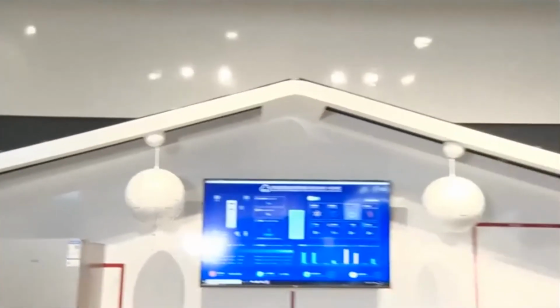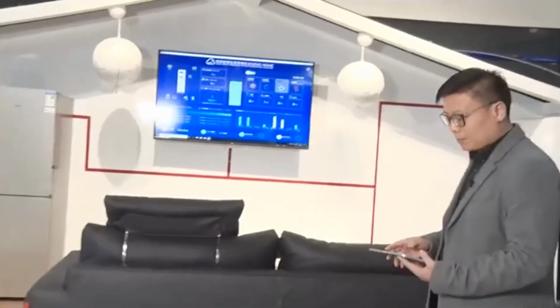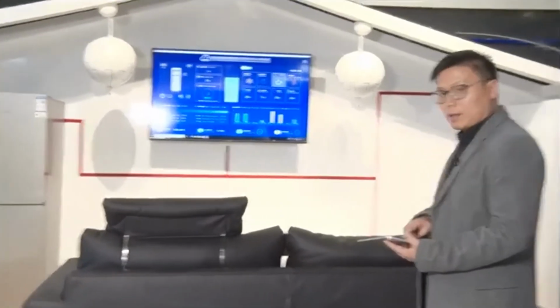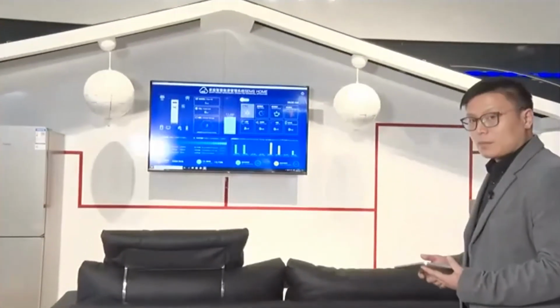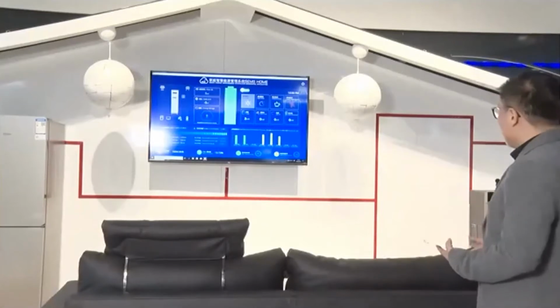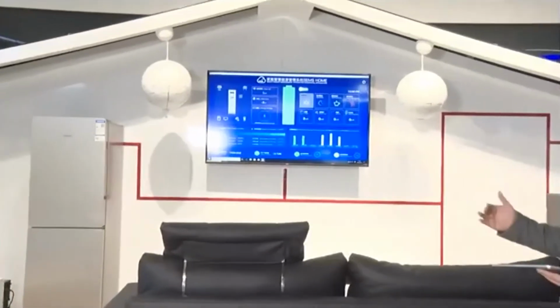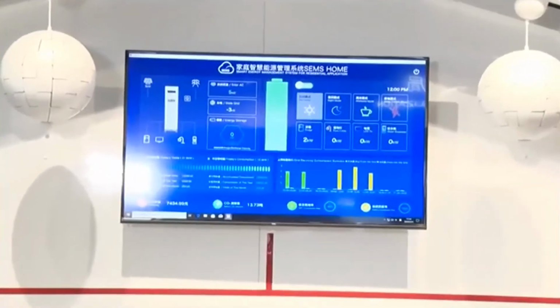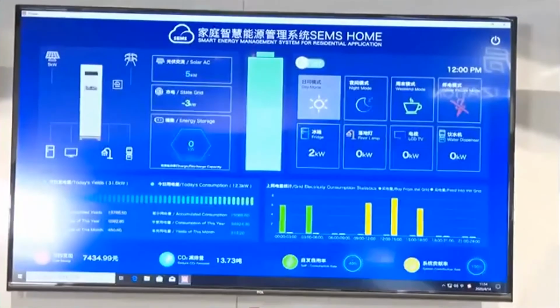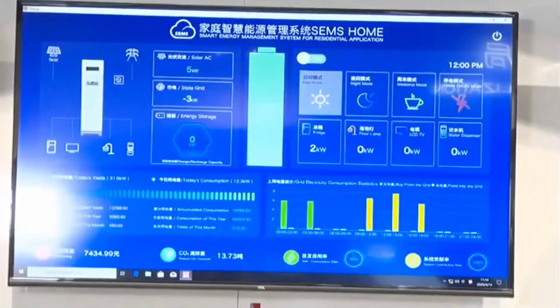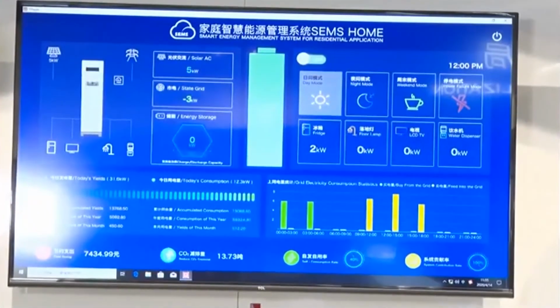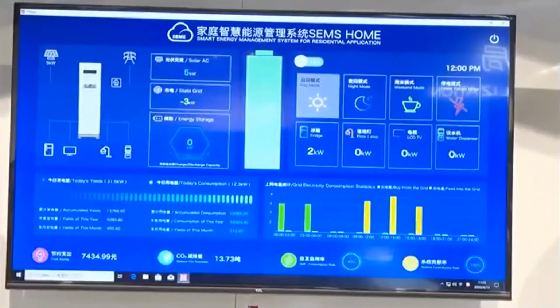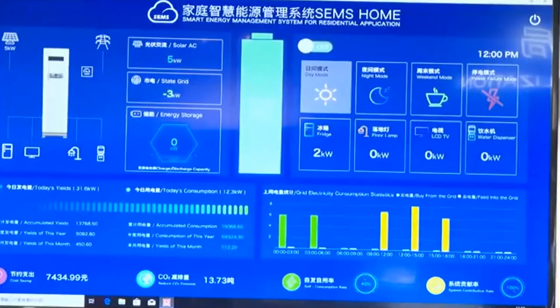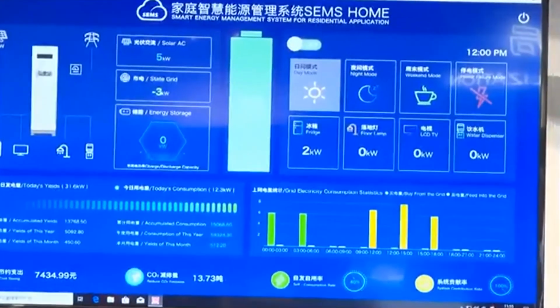Okay, let's get to the residential part. For the residential energy management system, we actually have four modes. We have the working daytime mode, the nighttime mode, the weekend mode, and the off-peak mode. The working daytime mode means we're out for work, right? There will not be much energy consumption at home. So your PV is generating, and through the hybrid inverter, it will feed the power into the grid.